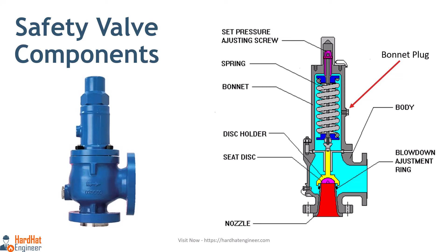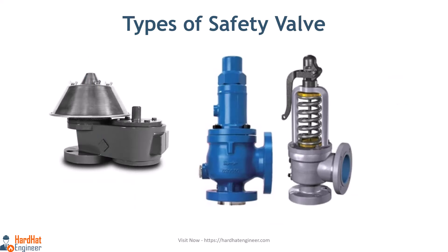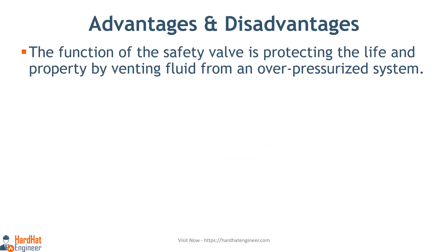Here you can see the conventional pressure relief valve. The main parts are the body, bonnet, disc, disc holder, seat, and spring. Based on seating material, conventional pressure relief valves are classified as metal-seated or soft-seated valves. The working principle is based on the balance of force — the spring load keeps the disc on the seat until the system pressure exceeds the spring force. The function of the safety valve is protecting life and property by venting fluid from an over-pressurized system.